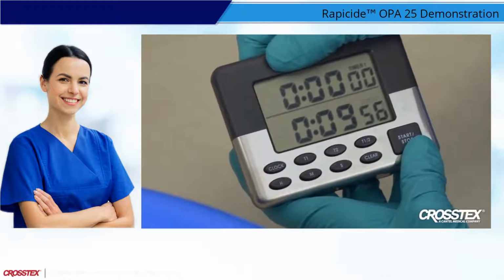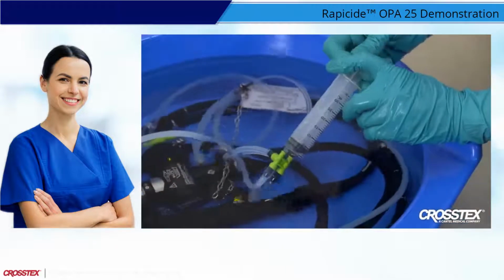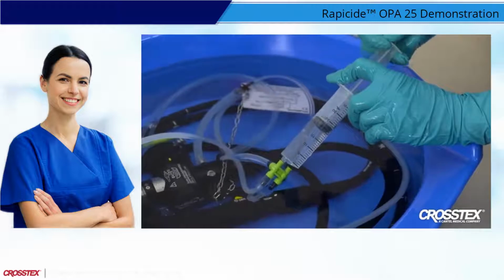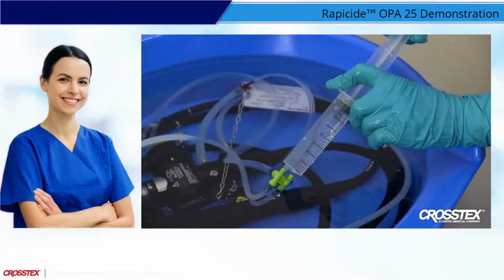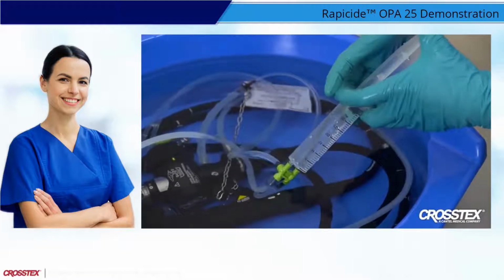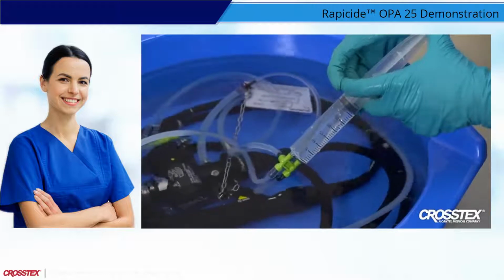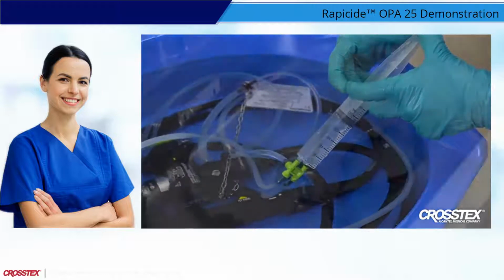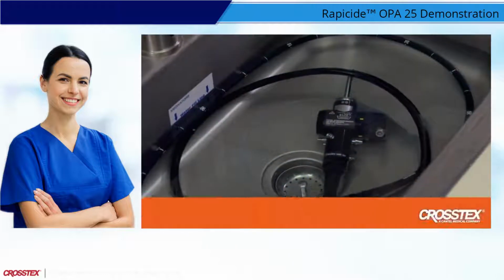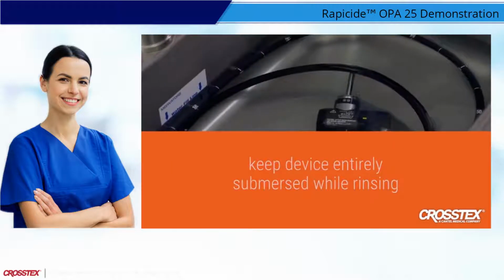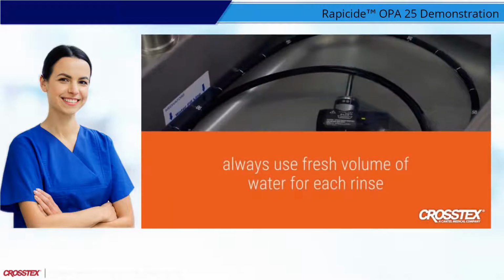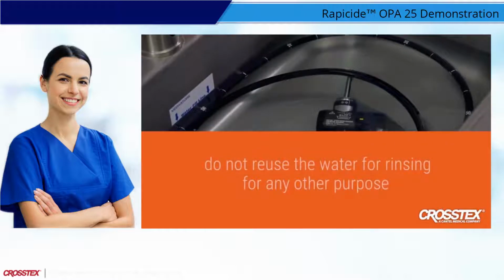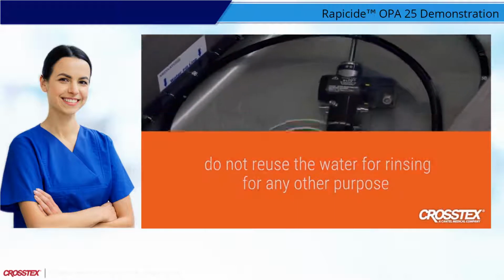Make sure all lumens are filled. Remove the device from the solution and rinse thoroughly according to the device manufacturer's rinsing instructions. In the absence of the device manufacturer's rinsing instructions, thoroughly rinse by immersing in a large volume of water. Keep the device entirely submerged while rinsing. Always use fresh volumes of water for each rinse. Do not reuse the water for rinsing for any other purpose.